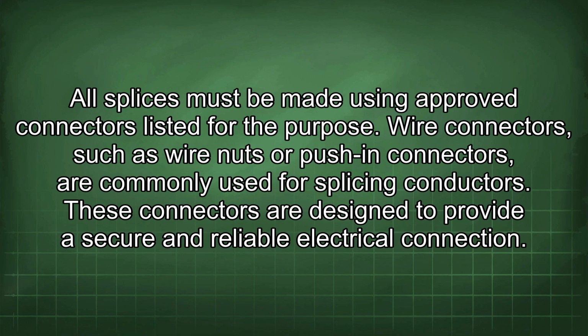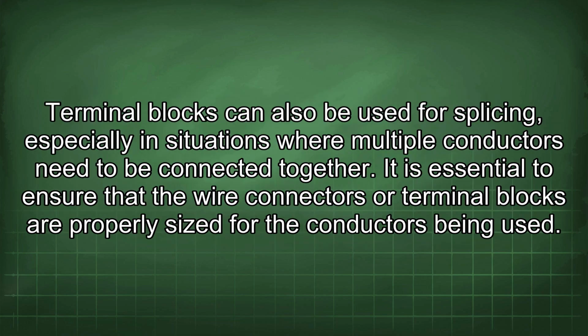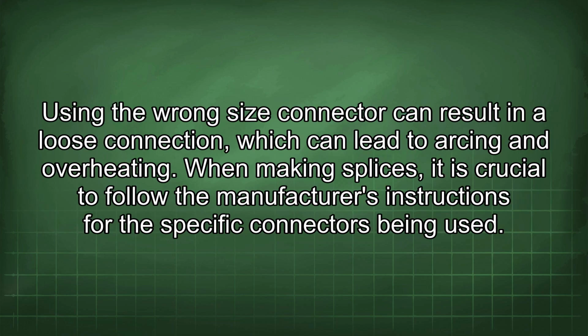Wire connectors, such as wire nuts or push-in connectors, are commonly used for splicing conductors. These connectors are designed to provide a secure and reliable electrical connection. Terminal blocks can also be used for splicing, especially in situations where multiple conductors need to be connected together. It is essential to ensure that the wire connectors or terminal blocks are properly sized for the conductors being used. Using the wrong size connector can result in a loose connection, which can lead to arcing and overheating.